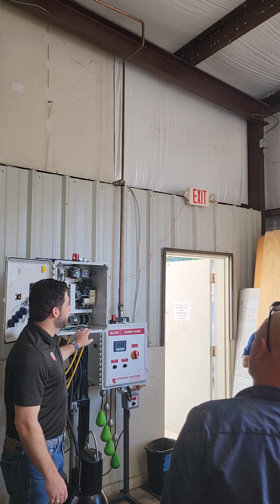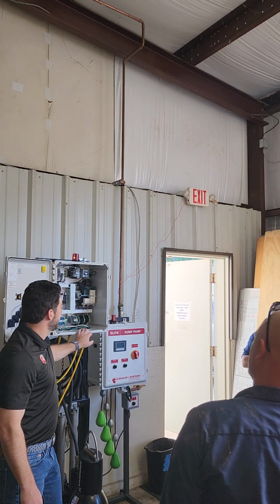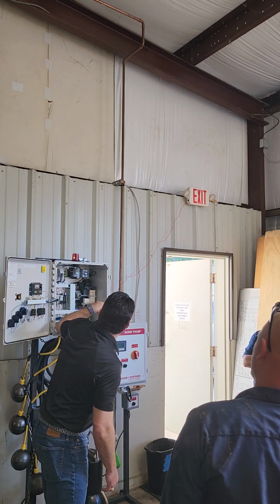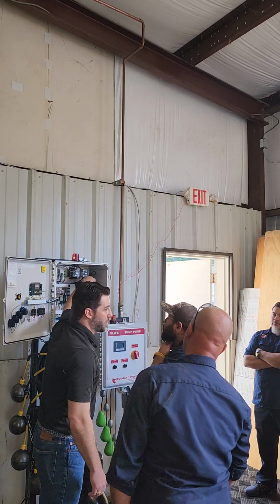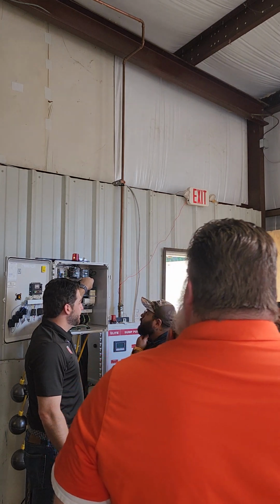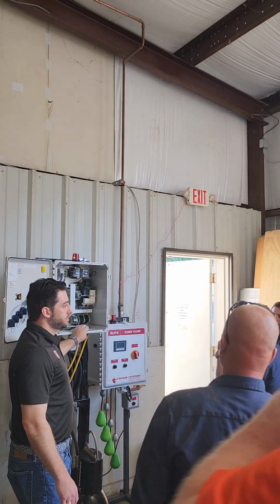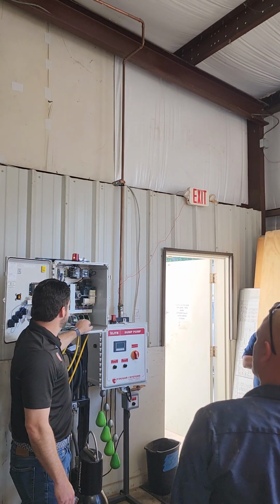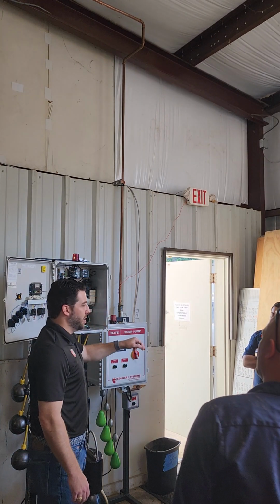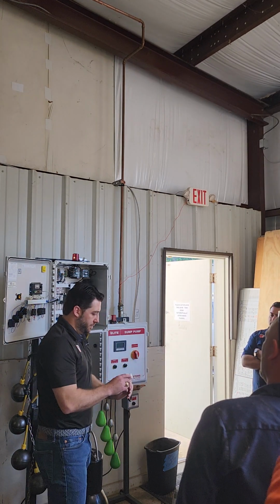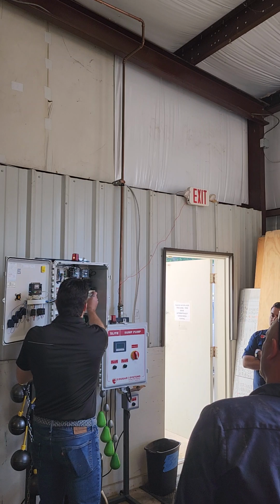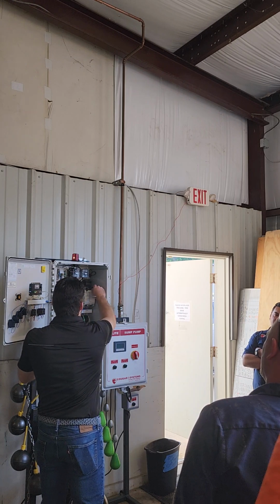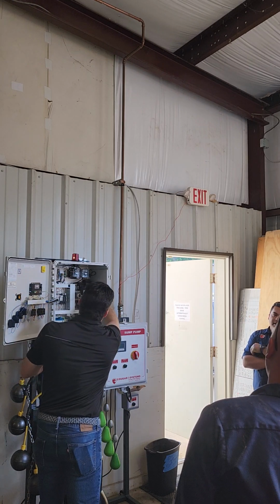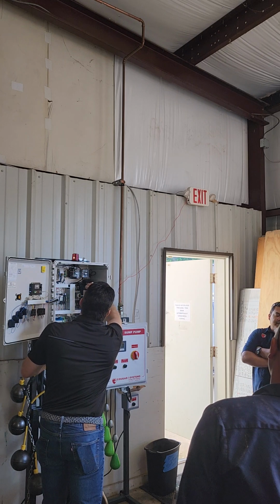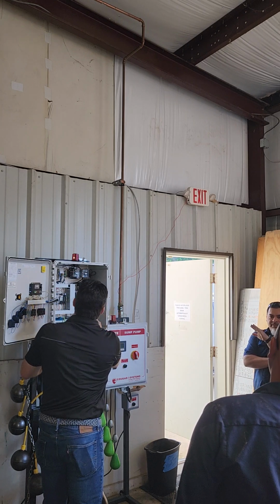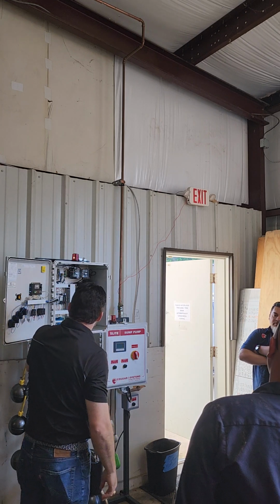How does it let you know? The little indicator right here moves from 0 to 1, and then it goes red if it's a direct short. So it's red if it's a direct short? Yeah, I believe it turns red if it's a direct short, and I think it says 0 or 1 if it's overload. You can tell when you turn it on.